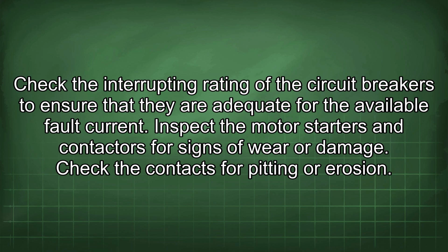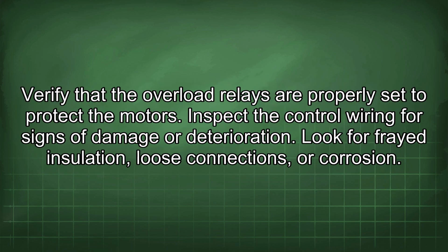Inspect the motor starters and contactors for signs of wear or damage. Check the contacts for pitting or erosion. Verify that the overload relays are properly set to protect the motors. Inspect the control wiring for signs of damage or deterioration. Look for frayed insulation, loose connections, or corrosion.